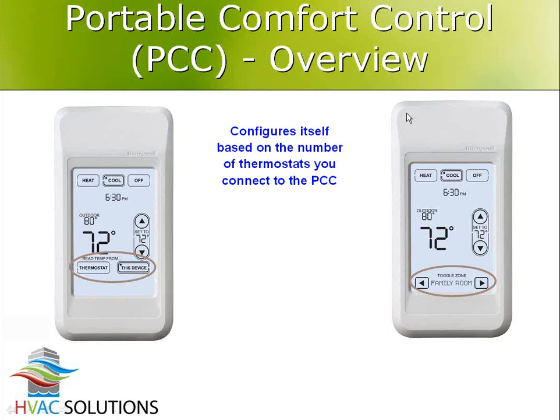On the right-hand side, it shows you a slightly different application. If you look at the bottom of that screen, it's hooked up to a zoning system, or a system that has multiple thermostats that aren't necessarily zoned on the air side, but maybe you have 3 furnaces, each one with its own stat. You could have one portable comfort control talking to all 3 of those. In those cases, you cannot make the portable comfort control be the thermostat on a zoning system because it wouldn't know which zone you were physically in, and it wouldn't know which damper to open. But you can still go look at all your zones, say, 6 zones you had in your house, and you can override their set points. But the sensing point would remain at the thermostat.